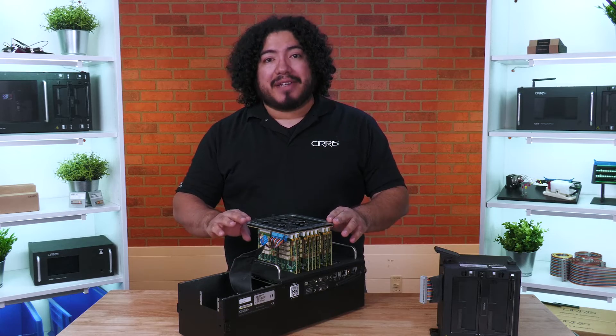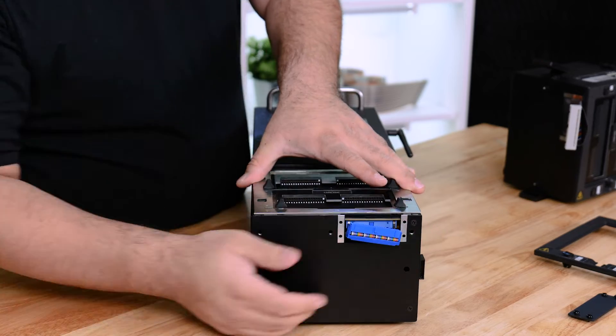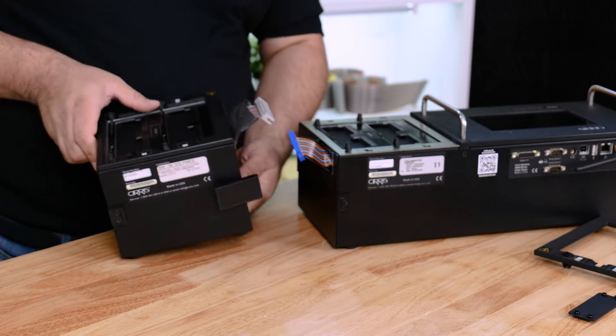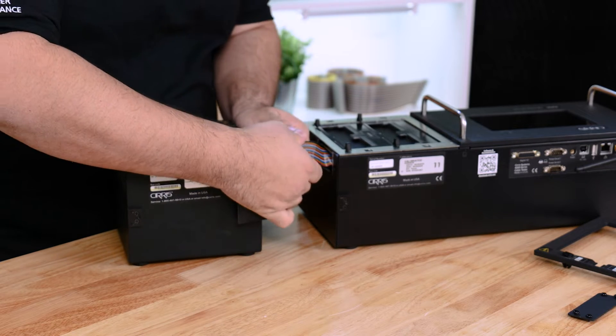Replace the scanner assembly with the daisy chain connector temporarily accessible through the expansion port. Do not replace the cover plate. Connect the ribbon cable on the expansion box to the daisy chain connector on the base tester.